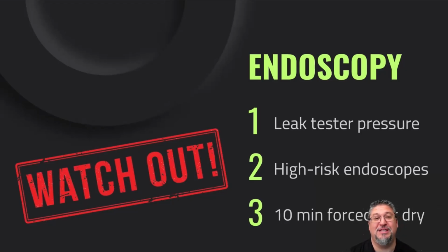Your high-risk endoscopes, the standards changed in 2021, 2022 when the new ST91 document came out. So your high-risk endoscopes, duodenoscopes, EBUS, all those kinds of things that are high risk, you do need to do cleaning verification testing every time. And that is a shall statement in the AAMI standards, which means if you're referencing AAMI standards in your policies, you need to be following what it says in the standards for high-risk endoscopes. So make sure there's cleaning verification testing on those high-risk scopes.